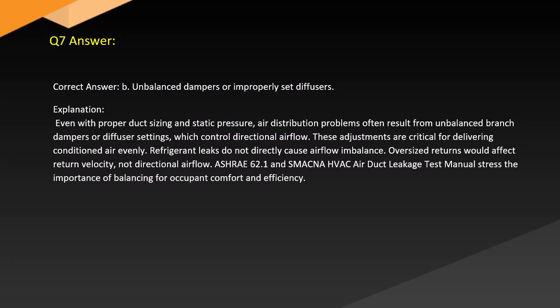Answer. Correct answer: B. Unbalanced dampers or improperly set diffusers. Explanation. Even with proper duct sizing and static pressure, air distribution problems often result from unbalanced branch dampers or diffuser settings, which control directional airflow. These adjustments are critical for delivering conditioned air evenly. Refrigerant leaks do not directly cause airflow imbalance. Oversized returns would affect return velocity, not directional airflow. ASHRAE 62.1 and the SMACNA HVAC Air Duct Leakage Test Manual stress the importance of balancing for occupant comfort and efficiency.